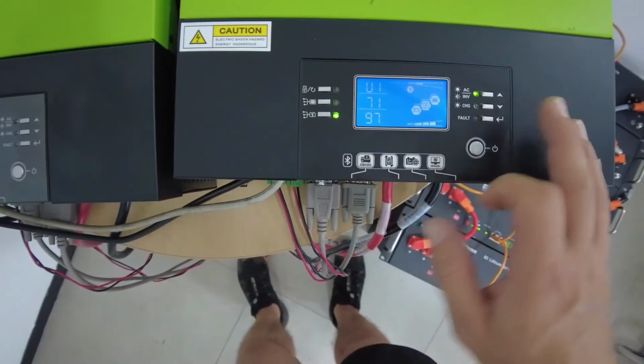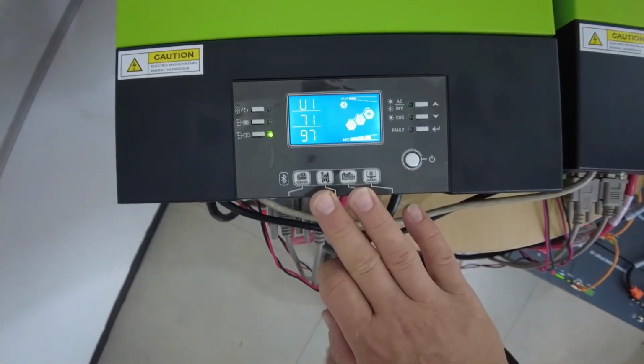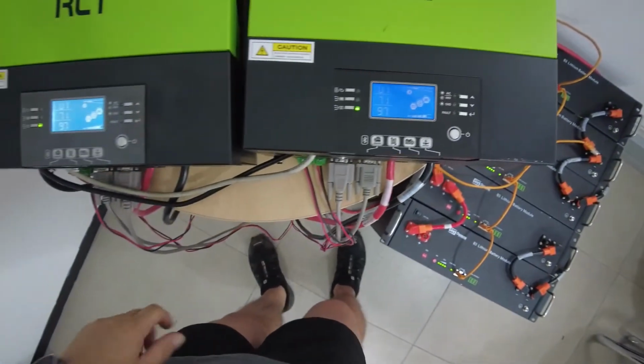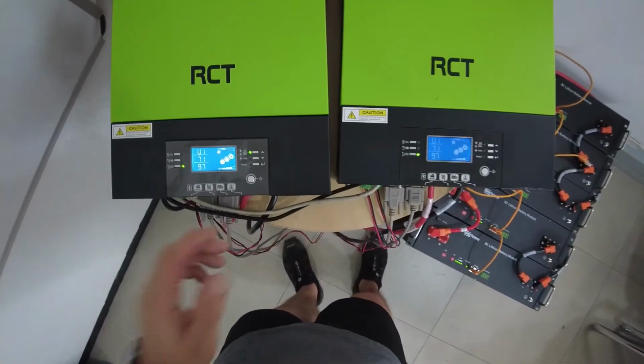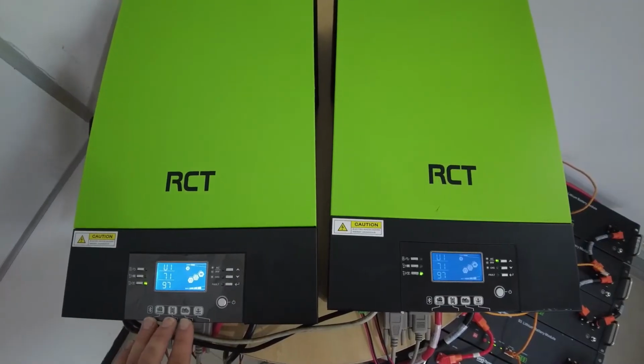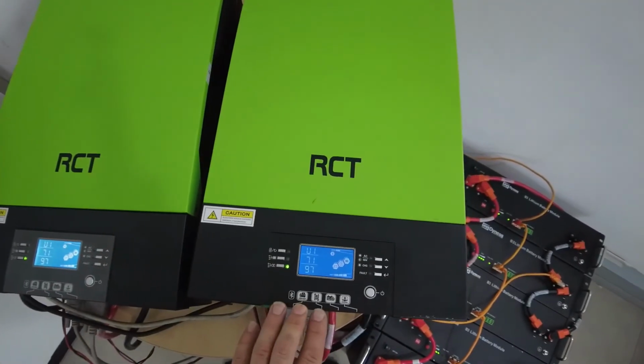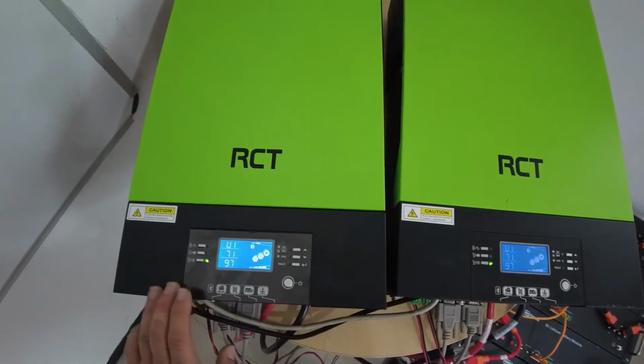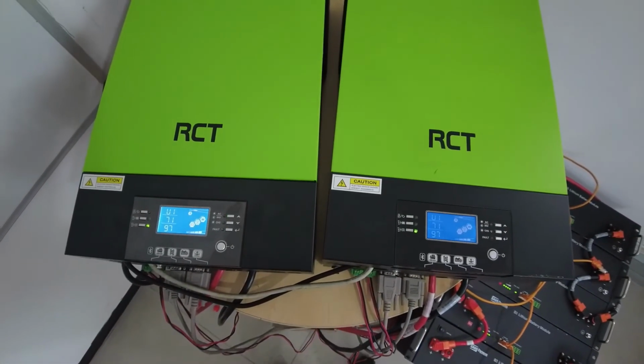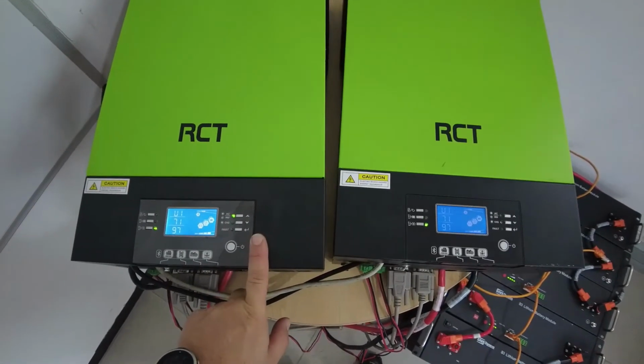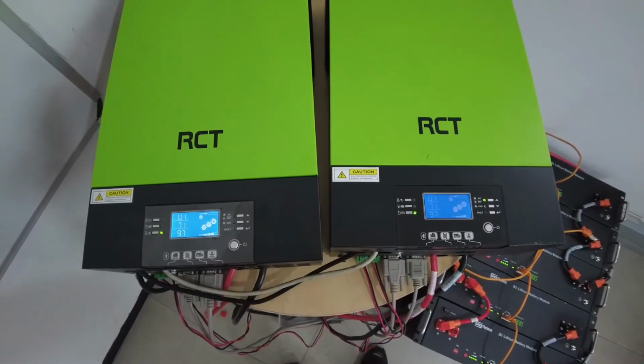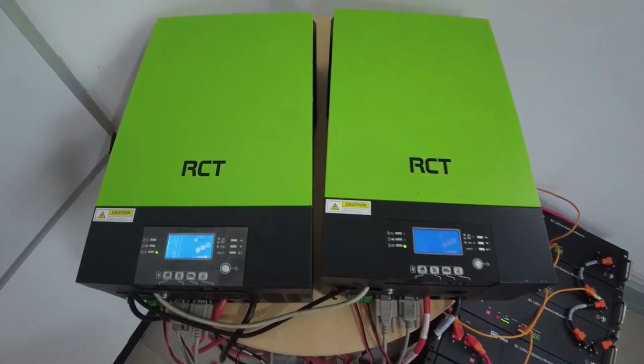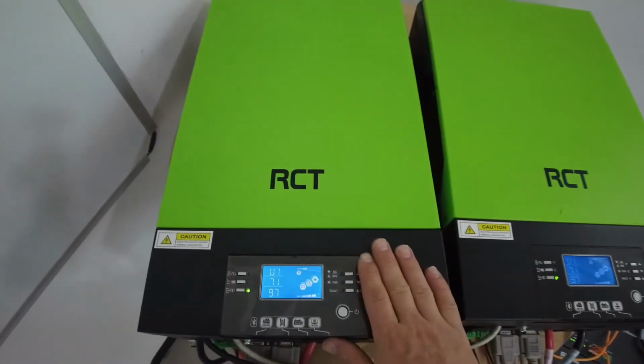Next up is your control board firmware, U1 7197, U1 7197. U1 is very important when you have a parallel connection. You do need to have your firmware the same on both inverters. If the hardware or the firmware is not the same, then the parallel system will not work. So it's very important, make sure that when you do installation, generally if you get the same inverters with the same order, it should be the same. Nonetheless, double check it when you do a firmware update that the firmware does correspond.